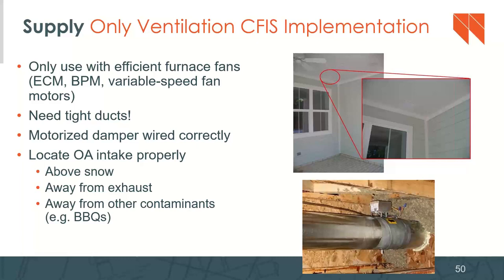A motorized damper that is wired correctly. In this case, this motorized damper in this design was not wired correctly. It was wired backwards so that when the air handler was on, it closed the damper, as opposed to we wanted the air handler to turn on and this damper to open to let that fresh air in, right? It was wired backwards. And then locate this outside air intake properly. So properly means above the snow line, right? So probably at least 2 feet off the ground. And if it's coming from a roof, you want that intake to be 2 feet above the roof deck. You want it to be away from other exhaust sources.